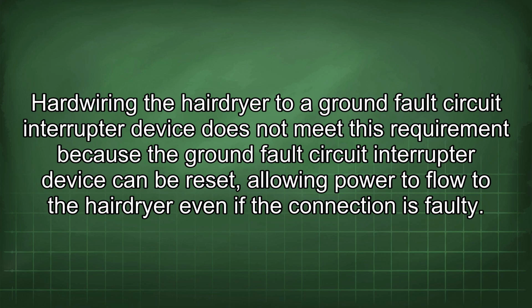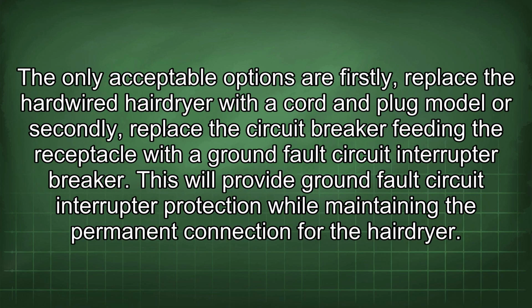Hardwiring the hairdryer to a ground fault circuit interrupter device does not meet this requirement because the ground fault circuit interrupter device can be reset, allowing power to flow to the hairdryer even if the connection is faulty. The only acceptable options are, firstly, replace the hardwired hairdryer with a cord and plug model, or secondly, replace the circuit breaker feeding the receptacle with a ground fault circuit interrupter breaker. This will provide ground fault circuit interrupter protection while maintaining the permanent connection for the hairdryer.